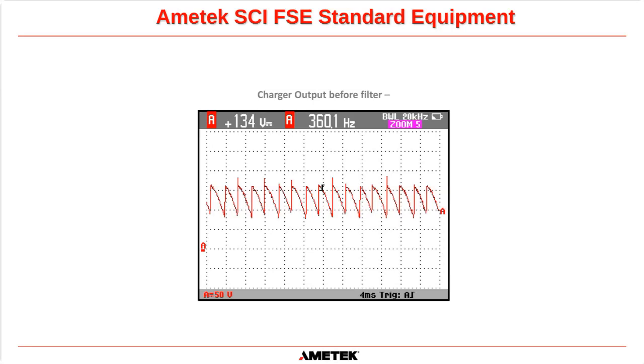And, you know, the oscilloscope is extremely useful when doing maintenance, because it can find things that sometimes you wouldn't find without being able to see it on an oscillograph. So this picture here shows you the charger output before it goes into the filter. And there are some circumstances, especially if there is a loose connection to one of the SCRs, that waveform there might be missing. And then we go 1, 2, 3, 4, 5, 6. So 1, 2, 3, 4, 5. That one there would be missing. Okay. In truth, that wouldn't affect the DC output voltage of the system. It's only when full load current would be required that these missing pulses would start to cause an issue.